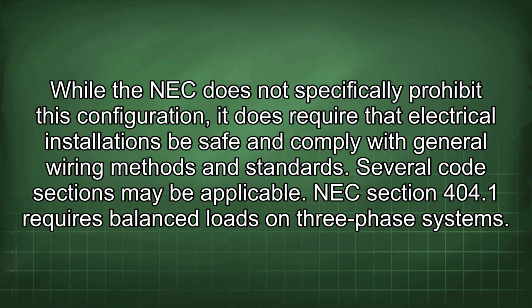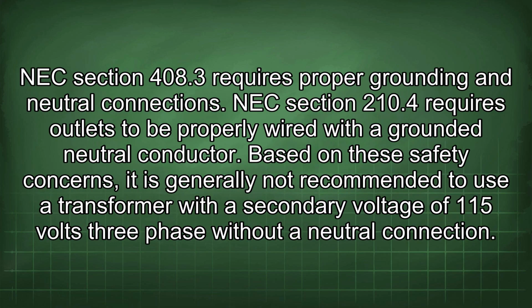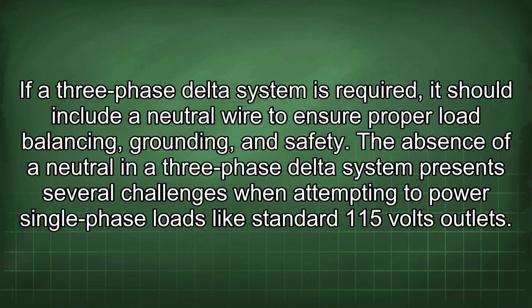Several code sections may be applicable. NEC Section 404.1 requires balanced loads on three-phase systems. NEC Section 408.3 requires proper grounding and neutral connections. NEC Section 210.4 requires outlets to be properly wired with a grounded neutral conductor. Based on these safety concerns, it is generally not recommended to use a transformer with a secondary voltage of 115 volts three-phase without a neutral connection. If a three-phase delta system is required, it should include a neutral wire to ensure proper load balancing, grounding, and safety.